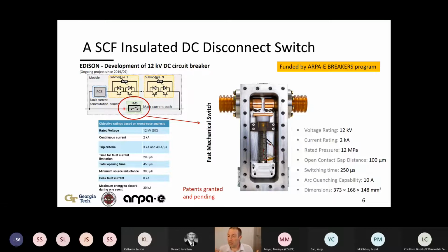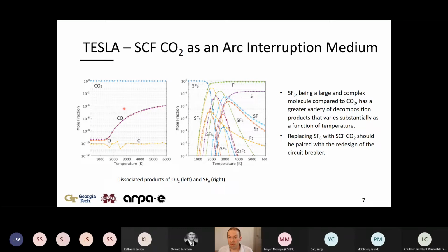Now, when it comes to arc quenching, there's a whole lot more that matters. It's not just viscosity and dielectric strength. What's just as important is really what happens with decomposition. So in an actual arc, when you ionize it and the gas decomposes, what do we end up with?